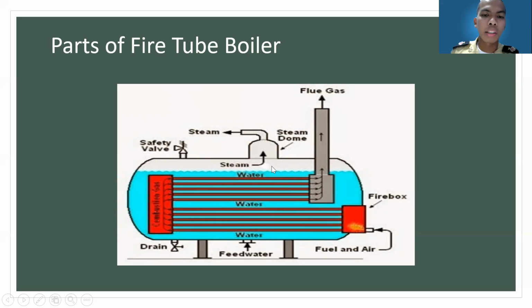And also the water level indicators. The operator should be aware of the water level throughout the operation of the boiler. Otherwise, the boiler cannot handle the pressure and can cause an explosion. Hence, to avoid these problems, a water level indicator must be mounted on the shell of the boiler.